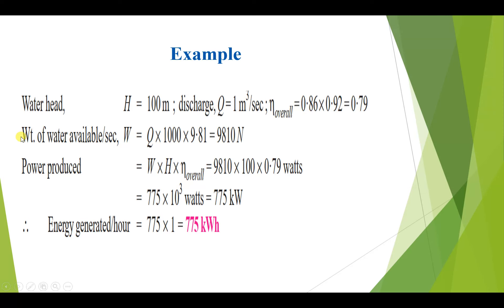In a similar way, we calculate the weight of water available per second, denoted W, equal to 1000 × 9.81 multiplied by the discharge rate. Taking a discharge rate of 1 cubic meter per second, we get 9810 Newtons — that is the weight of water available per second. The power produced is W × head × overall efficiency, giving us the result in Watts.